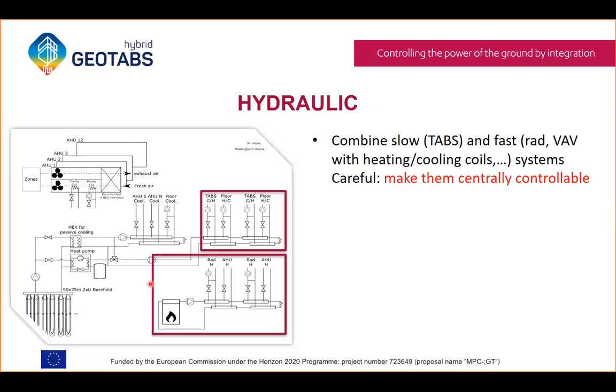The previous speakers have already emphasized the interest of having hybrid systems with both a slow system and a fast system, and MPC is able to use this. For example, on a sunny day at lunchtime, the building might need cooling, while in the morning after the night it might need some heating. So MPC might want to use the fast system just to give the necessary amount of heat to reach comfort early in the morning, without loading the TABS, to avoid overheating at lunchtime. But to make that possible, it's important that MPC can control both the slow and fast system centrally. So if your fast system is radiators with thermostatic valves, which are only manually controllable, you will hamper your MPC and actually prevent it from using your fast system, which is a pity in terms of optimality.